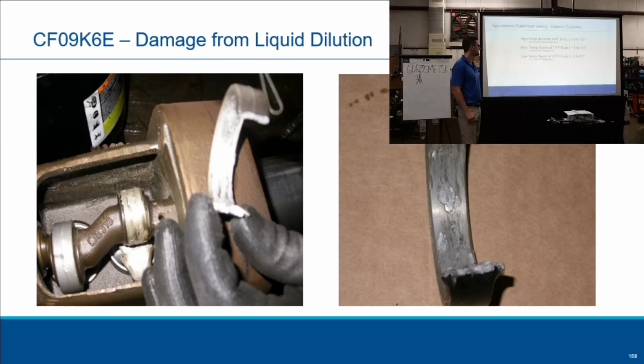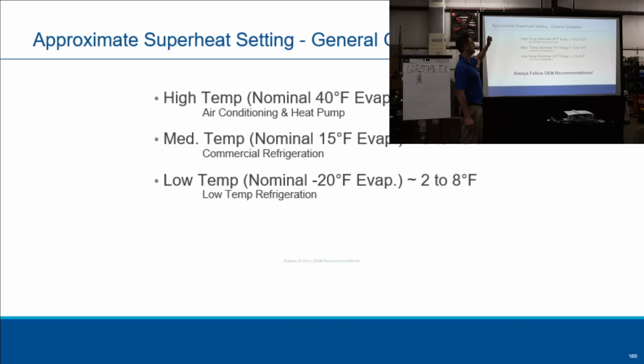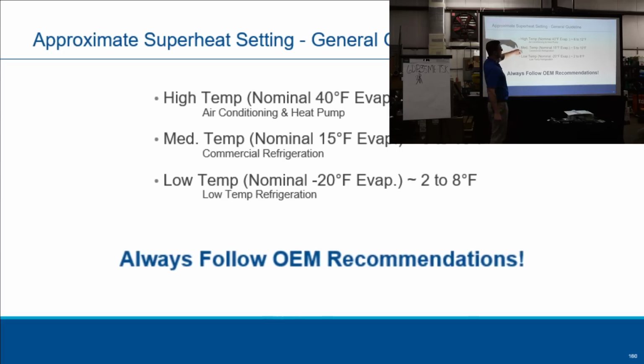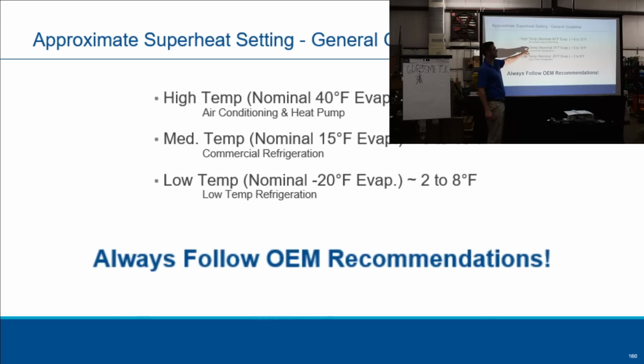Thank you, Don. So, guidelines. This is a rule of thumb. Low temp, 2 to 8; 5 to 10 medium temp; and 6 to 12 high temp for superheat. But what you need to do is follow the original manufacturer. The manufacturer of that evaporator is going to tell you, we want you running at 8 degrees superheat, we want you at 12 degrees superheat, or that plate heat exchanger. Right? They'll tell you what the superheat should be to be the most effective for that evaporator coil.